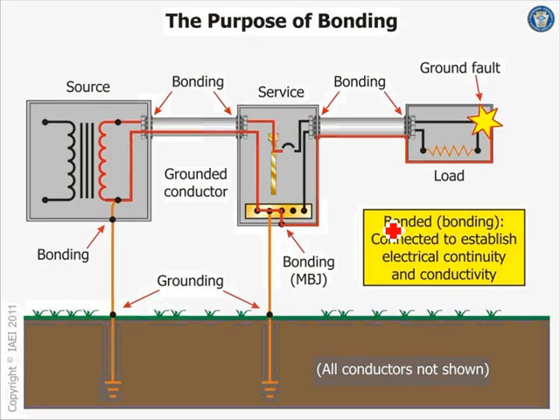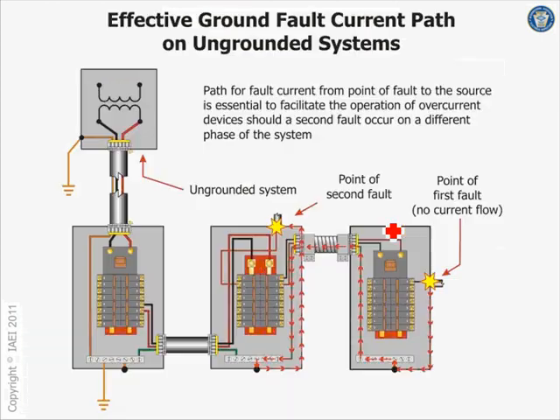Okay, so the purpose of bonding, we talked about bonding, guys. Look at the system. You have a ground fault that takes it all the way to my main bonding jumper. The main bonding jumper acts as the bridge that will carry this energy through the neutral back to the source. That's why they want you to bond the service disconnect enclosure to the neutral and to the equipment ground conductor right here. That is the effective ground fault path.